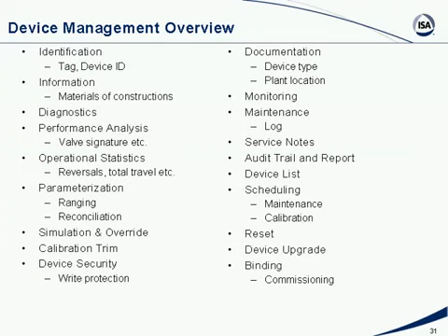The device ID is also used for a lot of other functions in an intelligent device management software. For example, based on the device ID, I can tell who is the manufacturer and what type of device I have. And based on this, the software can then pull up at the click of a button the correct manual for the device, let's say, or instruction sheet for performing calibration or some other function. Okay, and of course the same software can pull up information about the plant location, such as the hookup drawing, etc. Okay, I can do online monitoring to see the online dynamic parameters inside the device, so I can tell why the device is operating the way it is and figure out why it's not doing what I want it to do.